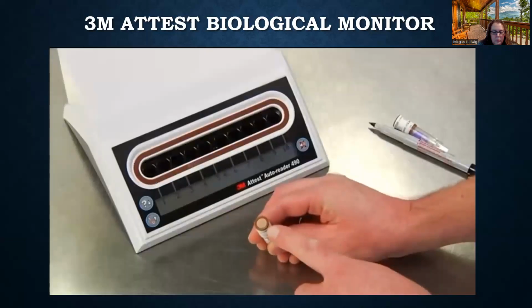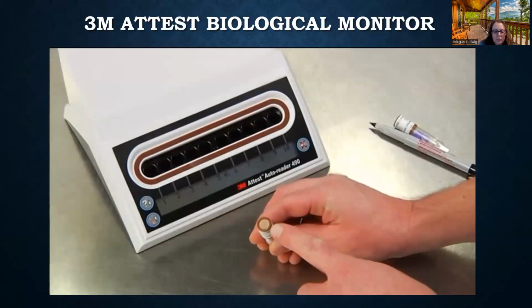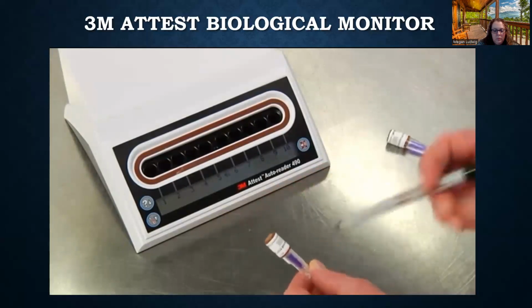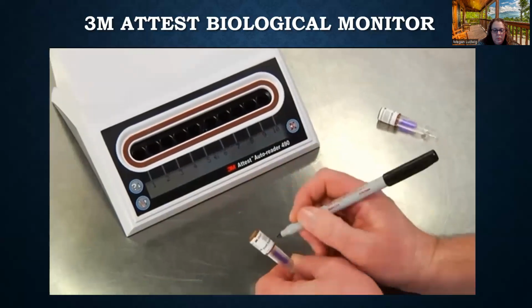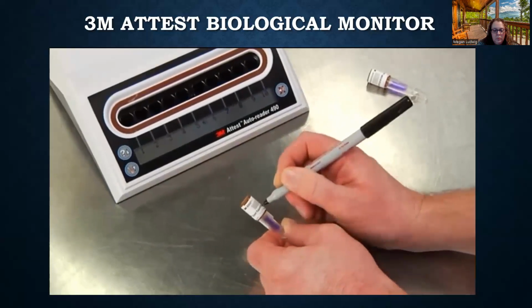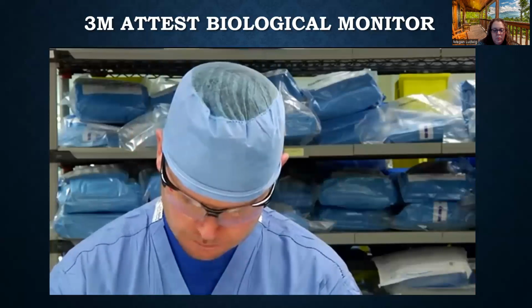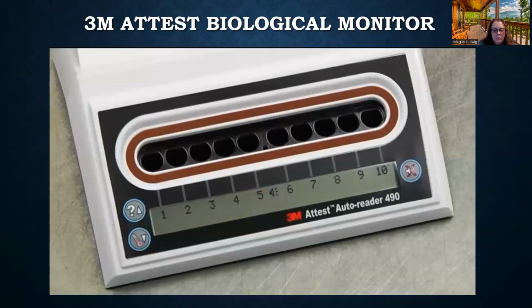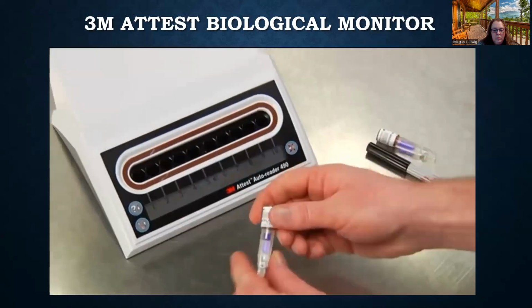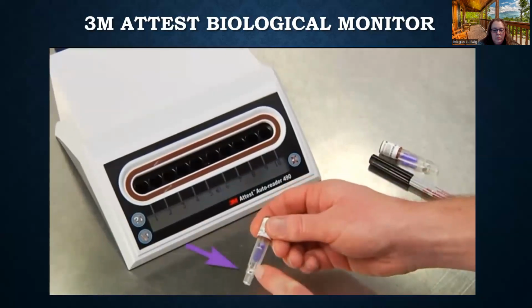Check the process indicator on the cap of the BI. A color change from pink to light brown confirms that the BI has been exposed to the steam process. Be sure to label the BI with the sterilizer, load number, and date. Wearing safety glasses, place the Attest Super Rapid BI in a matching color-coded Attest Auto-reader 490 incubation well. Make sure the flat side of the vial faces the back of the auto reader.